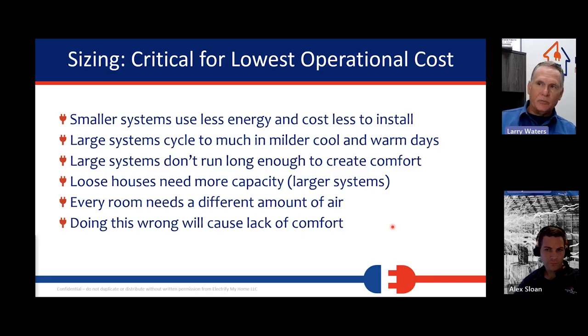Bigger systems are going to cycle too much in milder cold and warm, milder cold, and also just mild warm days. If we size a system to achieve full capacity, I just happen to have this load calc in front of me. This particular load calc I'm looking at, I did yesterday. This is sized for 104 degrees. Most of the summer it's not 104 degrees, but you want your system to work when it is 104 degrees. So we size it for that. So if I'm sizing a single stage system to cool your house when it's 104 degrees outside, what's it going to do when it's 89 degrees and you just want the house to be cool? It's going to be way oversized. It's going to turn on and off a lot. It's going to pull a lot of locked rotor amps every time it starts up, and it's going to waste a lot of energy.